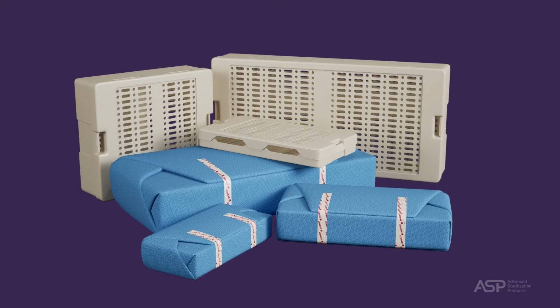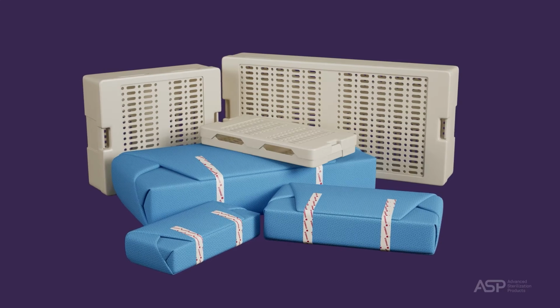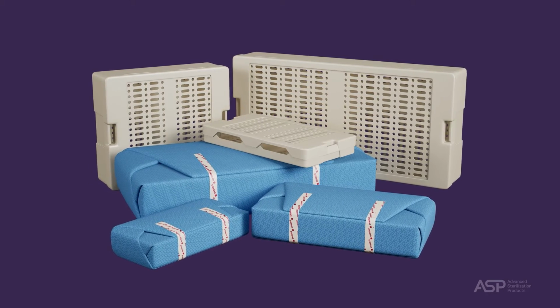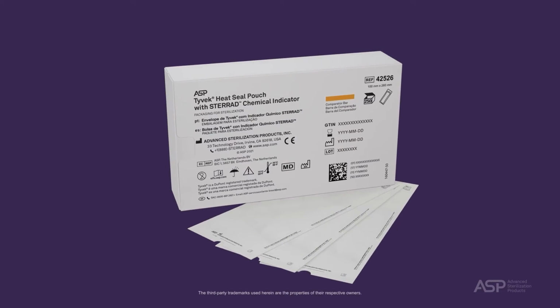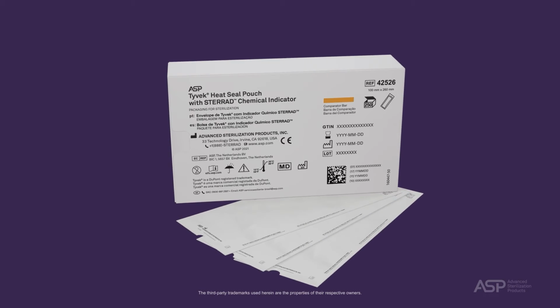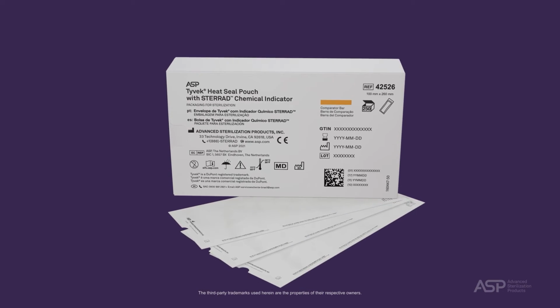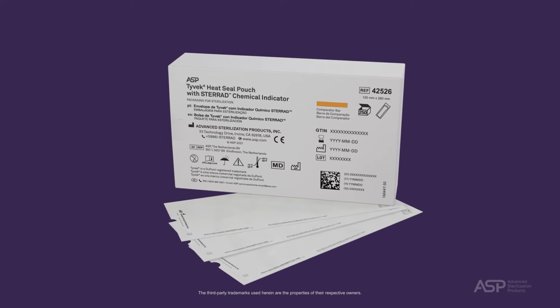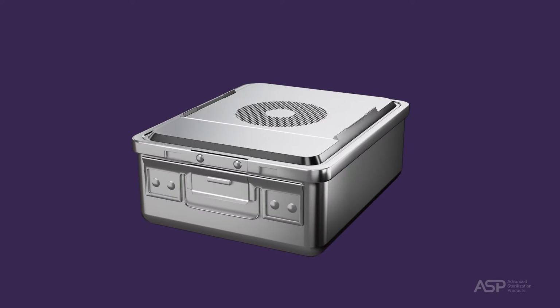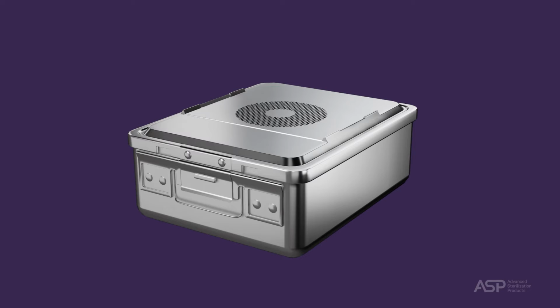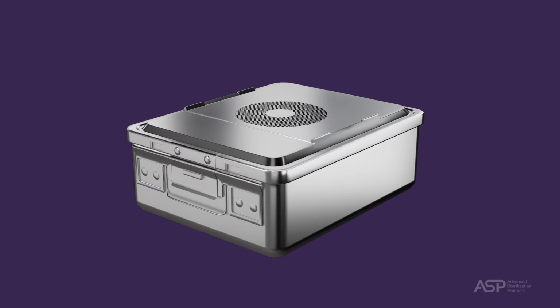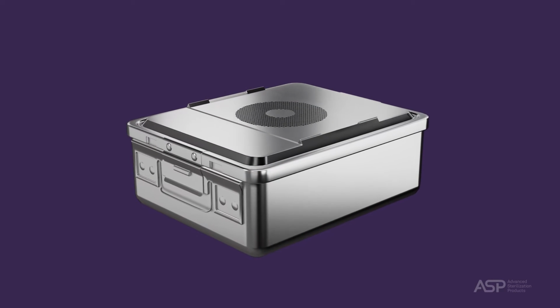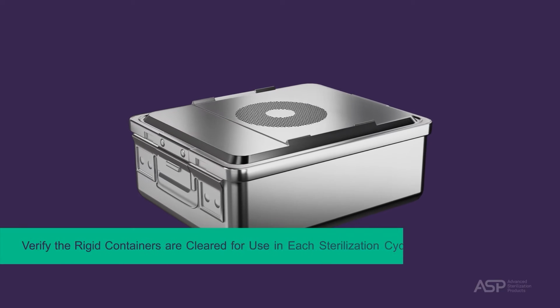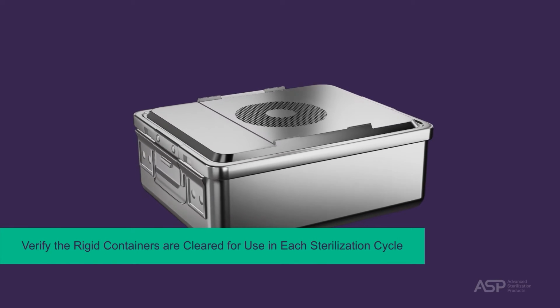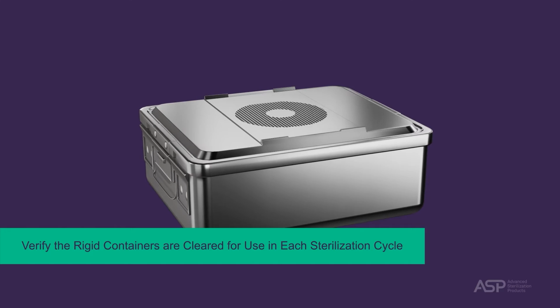Use only STERRAD sterilizer-compatible polypropylene sterilization wrap and Tyvek pouches. Tyvek pouches and rolls with STERRAD chemical indicator (CI) strips are the only pouches and rolls available on the market that are validated by ASP. If you are using rigid containers cleared by the FDA for use in the STERRAD NX Sterilizer, follow the instructions for use provided by the manufacturer. Verify that the rigid containers are cleared for use in each sterilization cycle.